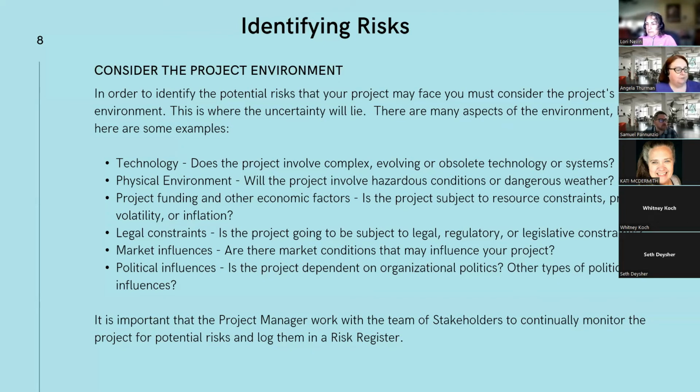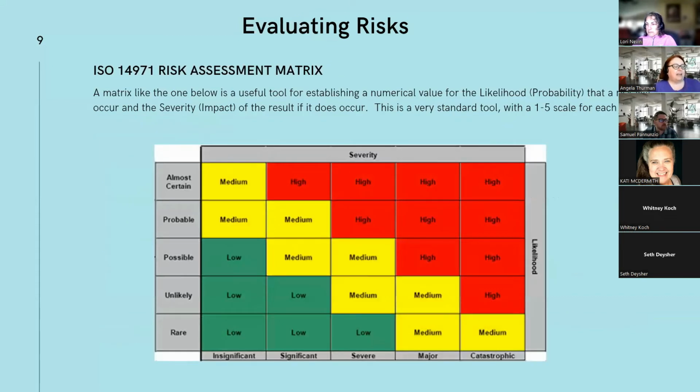Okay, let's move on. So now we're going to evaluate the risks that we've identified. So the ISO 14971 risk assessment matrix. So this is a tool you may see used frequently. The ISO actually no longer requires a risk assessment matrix, but it's still a very standard tool.